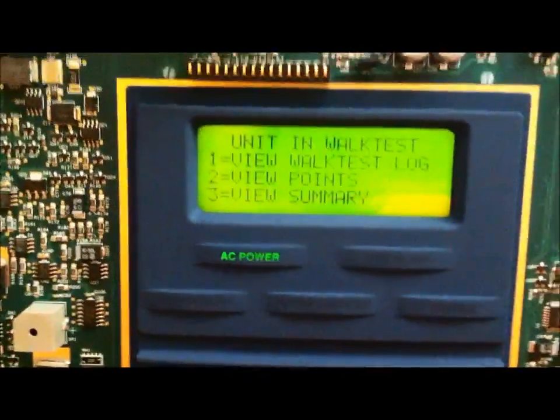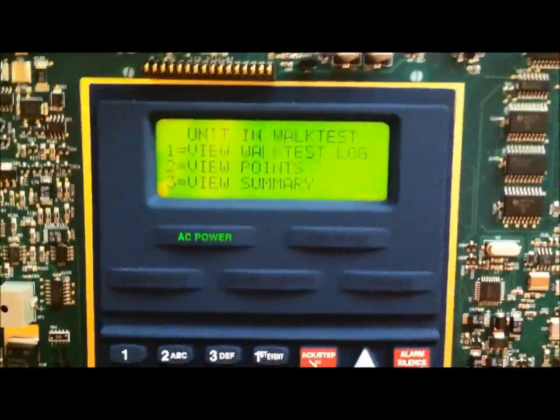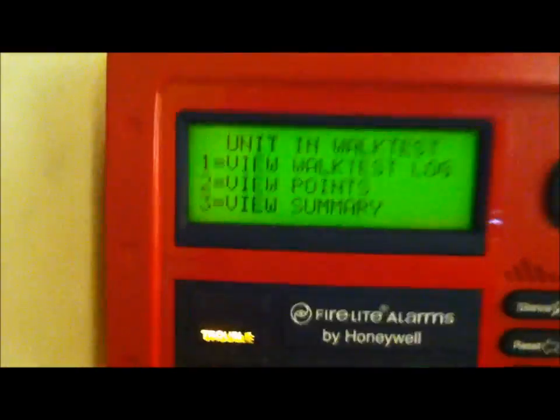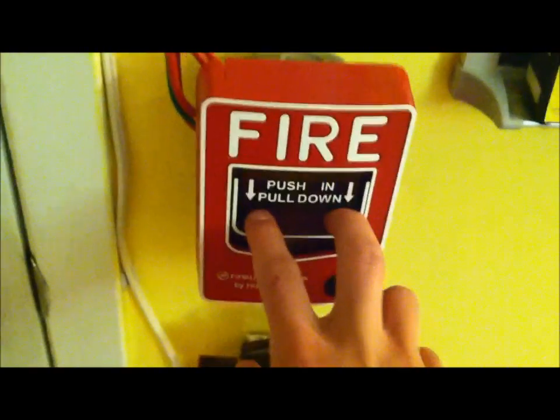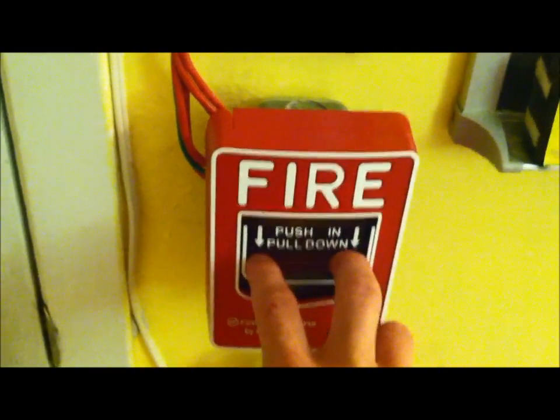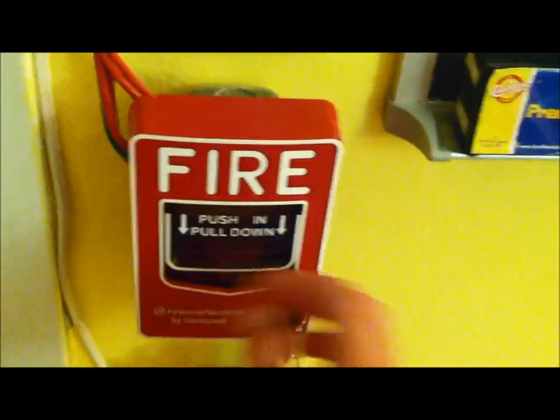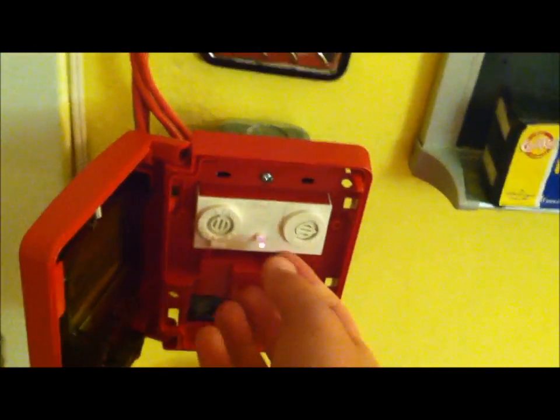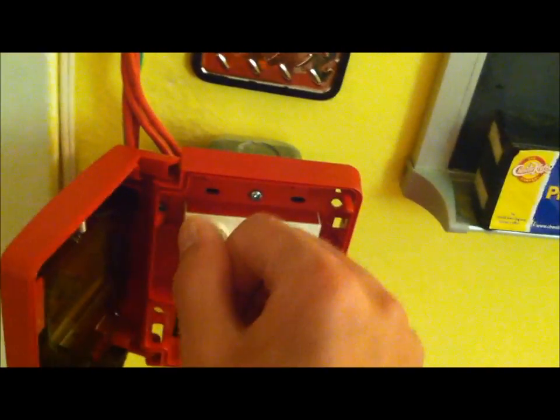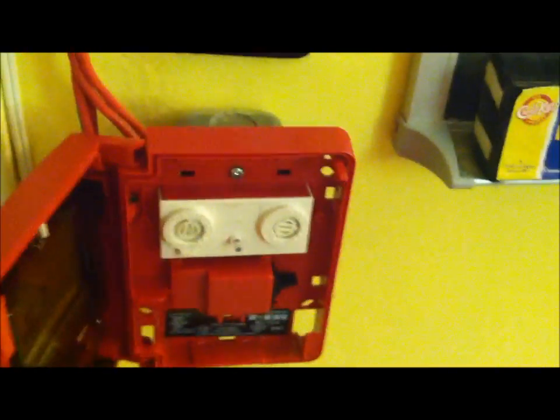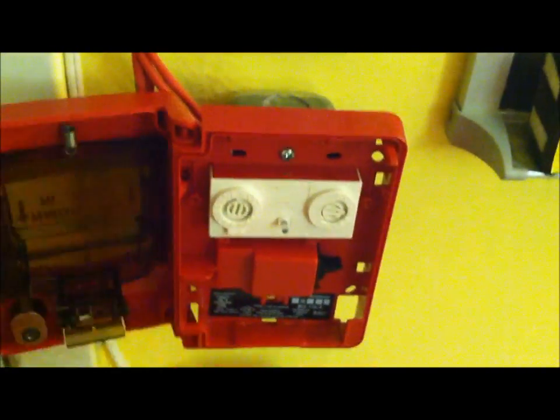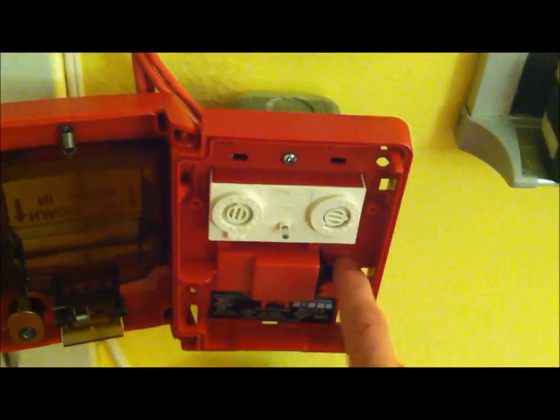I'm going to activate two devices and then show you how it works. I'm going to go over here to my pull station and you can see the annunciator right here showing the same information. This one is Monitor Module 4 and it is listed as Front Entrance Zone 1. With the walk test mode, a lot of people would just kind of flip the switch or key activate it if it's like a simplex T-bar or a Firelight BG8 because it's less time consuming than pulling and opening it.